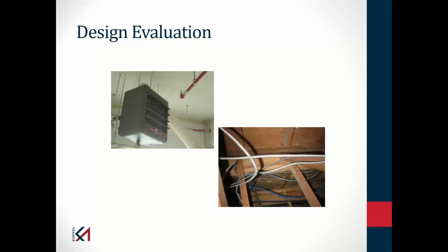Design evaluation. So I struggle with this as a member of the NFPA 25 committee, because we're going to tell you that that is the responsibility of the owner. Most owners, remember, we're putting sprinkler systems in most buildings that are being built today, low-rise office buildings, etc. Most owners don't have that expertise to know, and we spent a couple minutes talking about occupancy hazard. Most owners don't know that. Most owners don't know whether I need to have sprinklers in that concealed combustible space that I see in the lower right-hand corner.